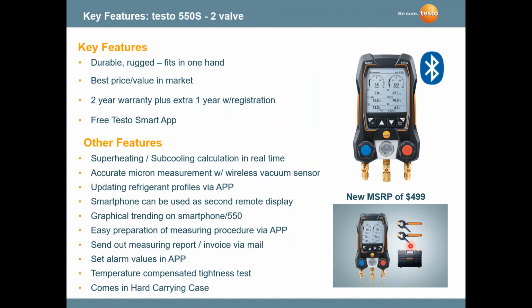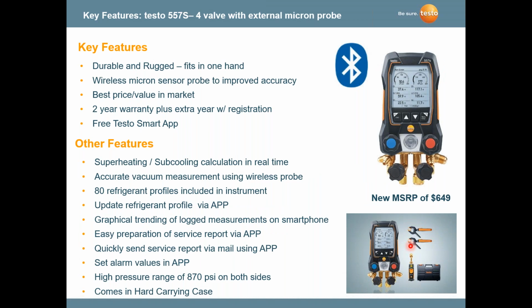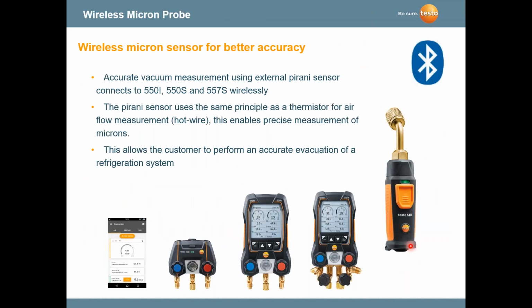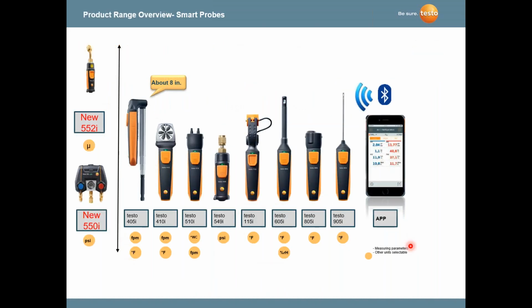So again, quickly, I'm not going to go through this, but 550S is a 2-valve. We have a 2-year warranty, plus we have 1-year registration. You get an extra year if you register the unit. So you get up to 3-year warranty on these instruments. This is the 4-valve configuration. Again, 3-year warranty on registration. Again, we talked about accuracy on the micron sensor. It's a separate test. It is Bluetoothed into the 550S and the 557S.